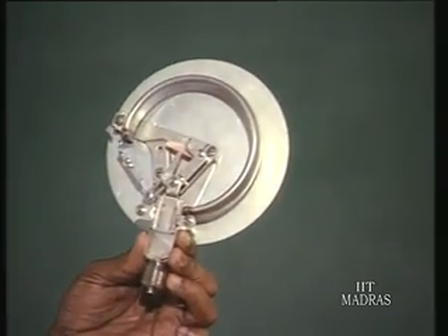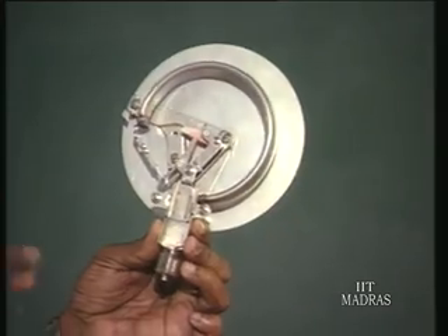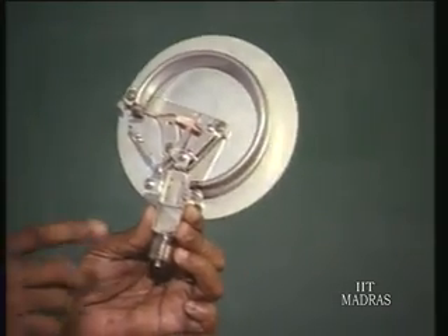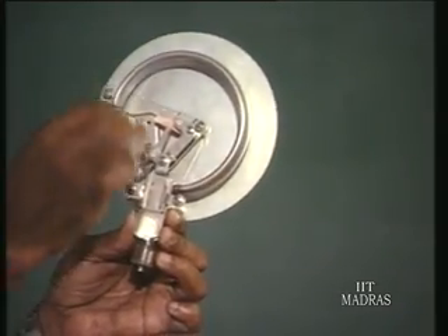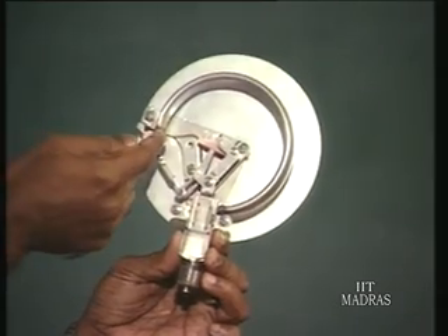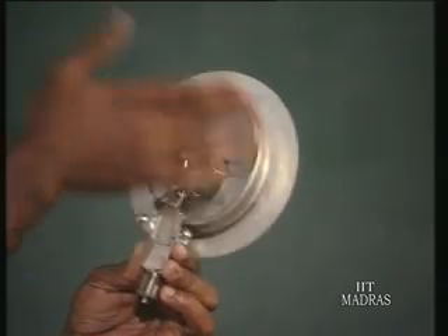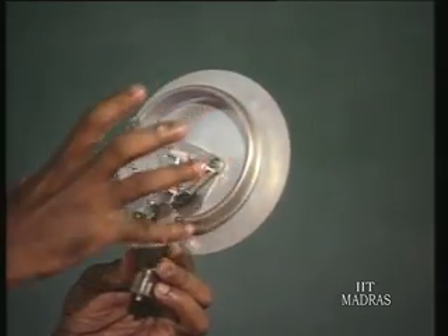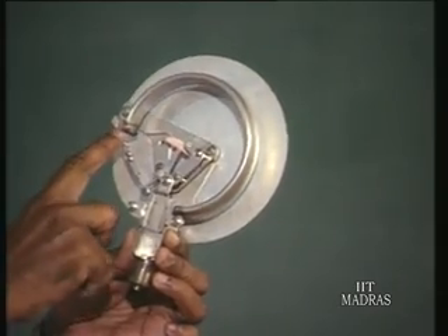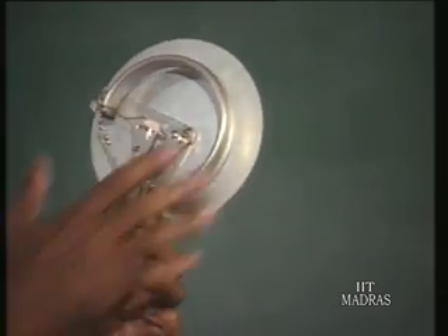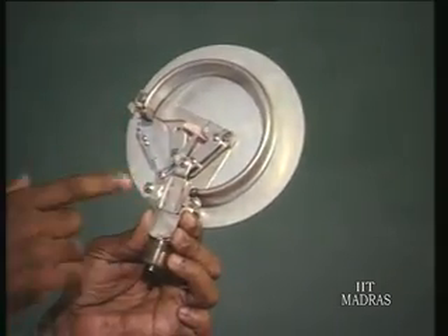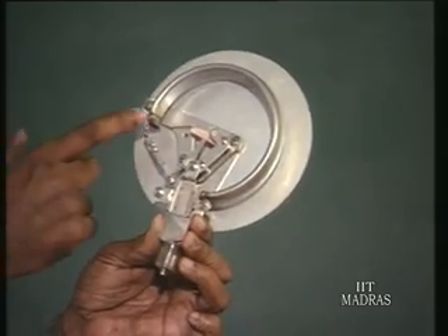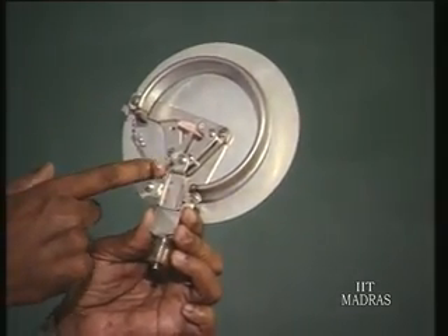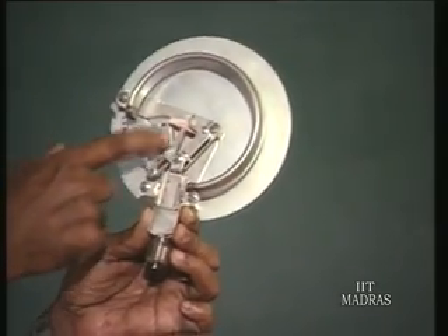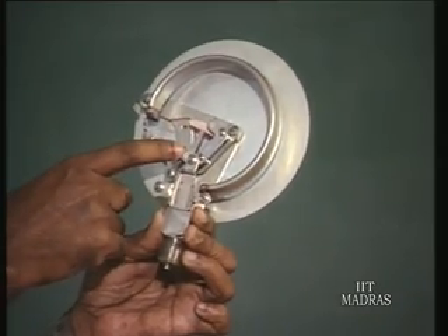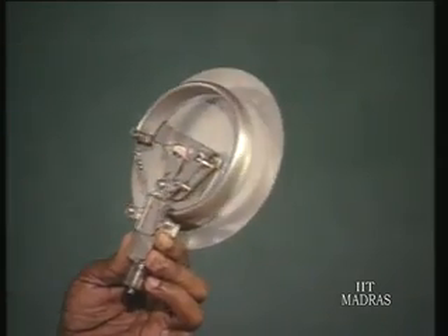If it is zigzag without any air, when you put air, it assumes a perfect round. Similarly, when pressure air comes to this end, it tries to move. If it is a closed one, it will assume a perfect round, and if it is a free end, this free end will be trying to extend. So when pressure is there, it is trying to extend. This motion is picked up by the linkage, and then it is given to another pivot mechanism, and at the end of the pivot, we have got this gear.